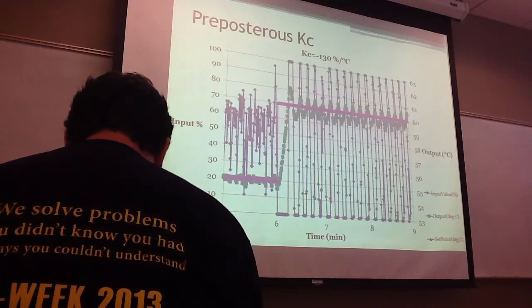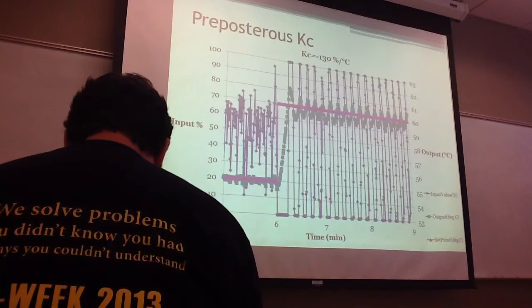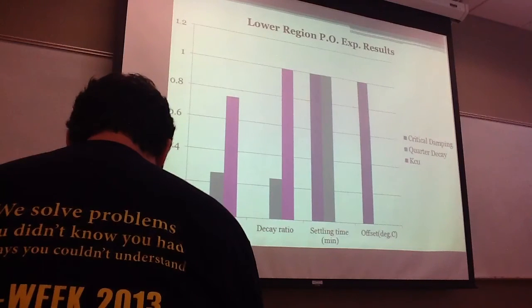This is what the modeling is showing, and it doesn't know. It's just crazy right now. All it knows is 0% and 100%. It gets too hot. Well, let's turn the fan on 100%. Oh, it's too cold now. Well, let's just turn it off. There's no in between. So it just gets crazy, and so it oscillates. There's no in between for it to instead level out.